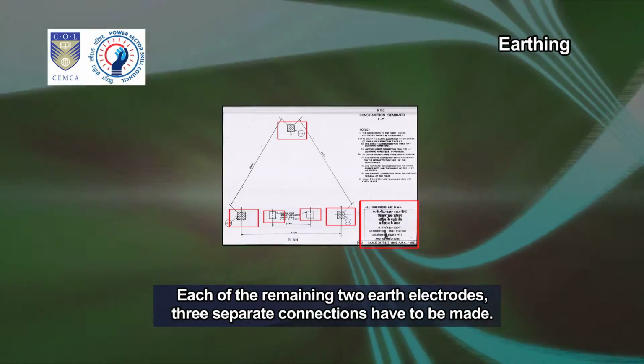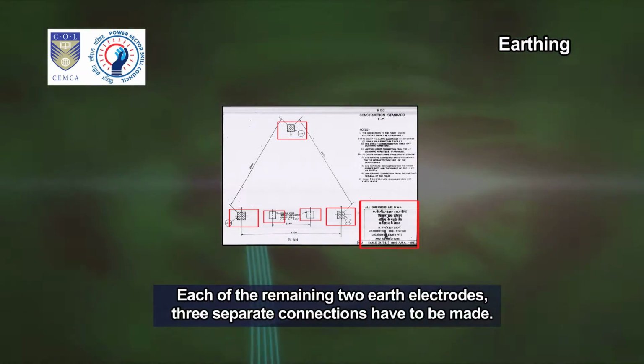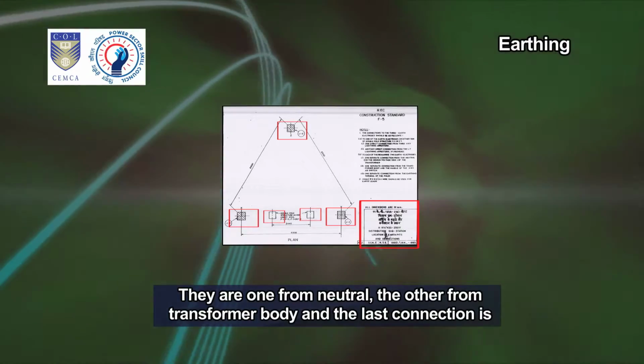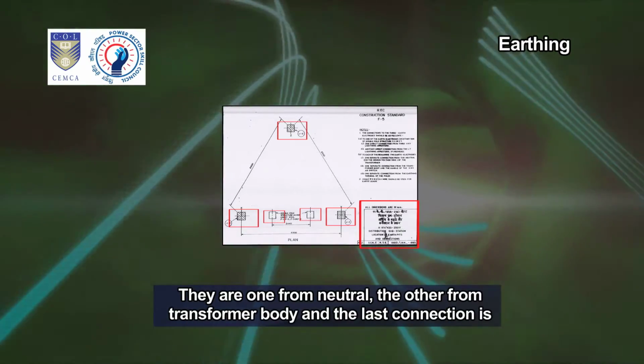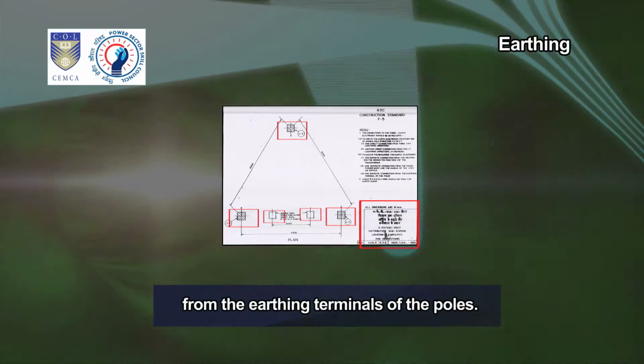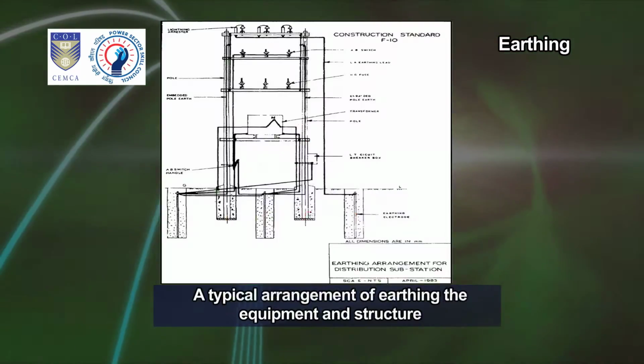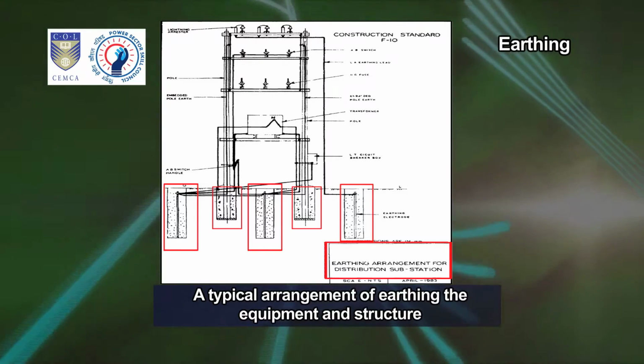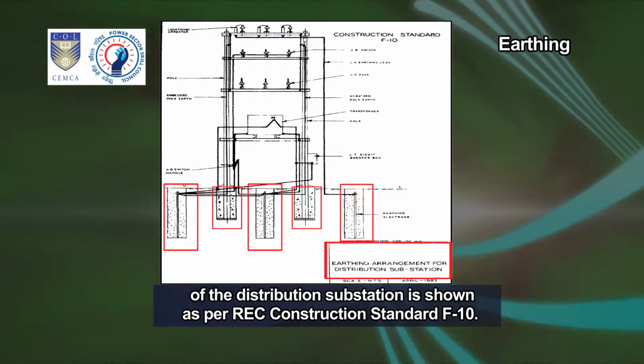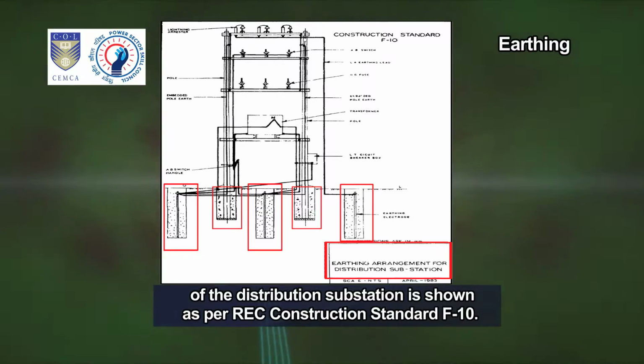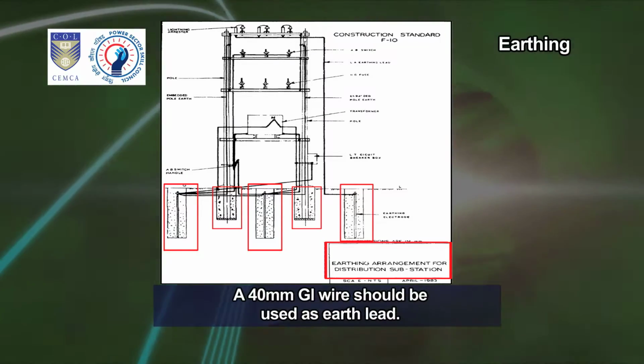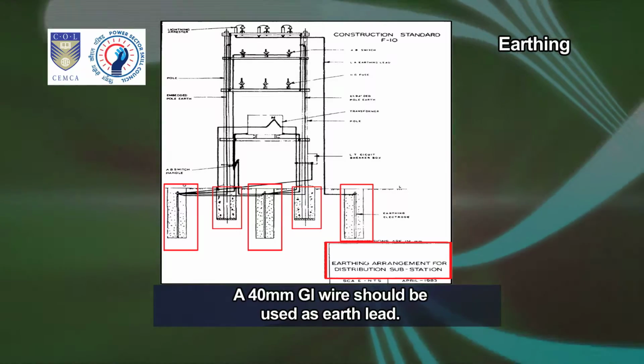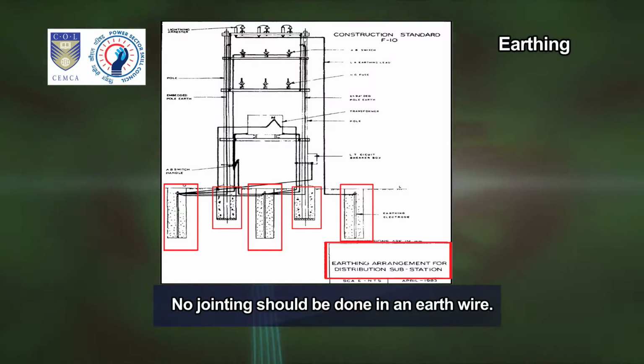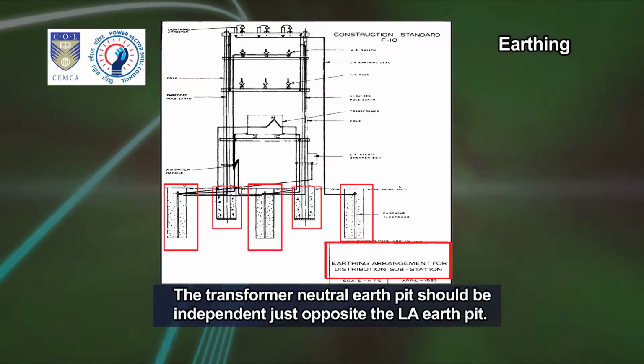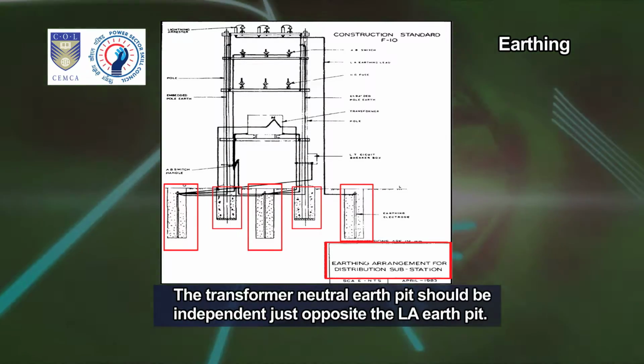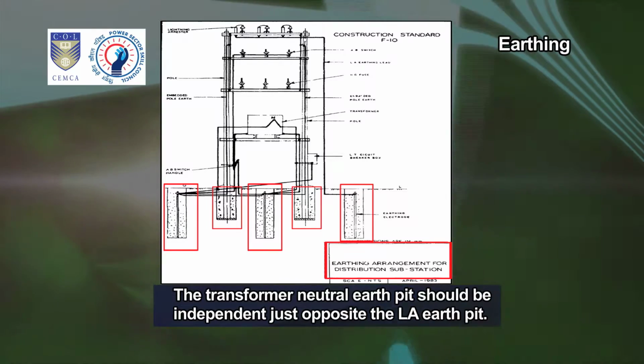For each of the remaining two earth electrodes, 3 separate connections have to be made. They are one from the neutral, another from the transformer body, and the last from the earthing terminals of the poles. A typical arrangement of earthing the equipment and structure of the distribution substation is shown as per REC construction standard F10. A 40 mm GI wire should be used as earth lead. No jointing should be done in an earth wire. The transformer neutral earth pit should be independent, just opposite the LA earth pit.